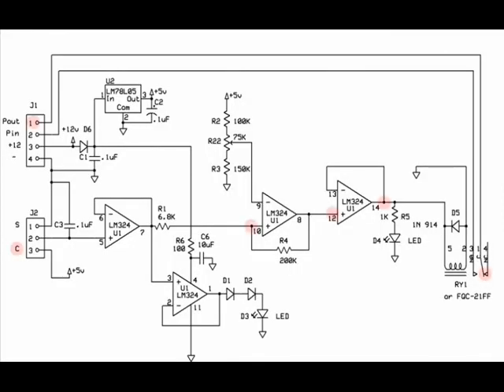When heat is available, the pump turns on. When heat is not available, the pump turns off. A relay is used to transfer power to the pump, but the life expectancy of a relay is limited — in the same way people have a limited number of steps. Rapid on-off cycles are known as chatter. Slow chatter occurs when the latch circuit on the controller is inadequate. Fast chatter occurs on PV-powered systems without battery backups, or without pump start-up protection.